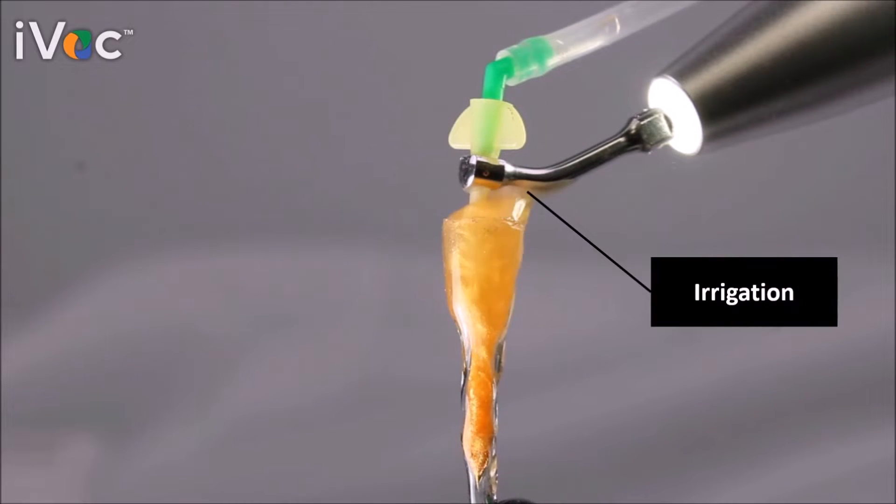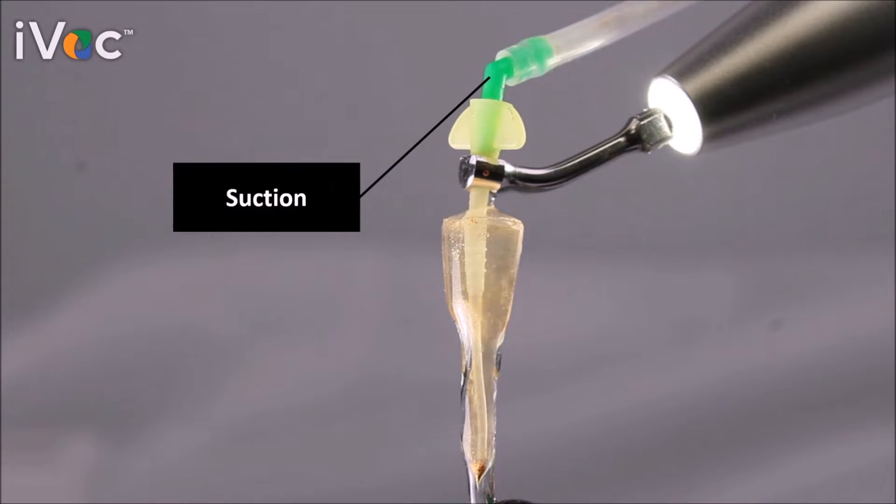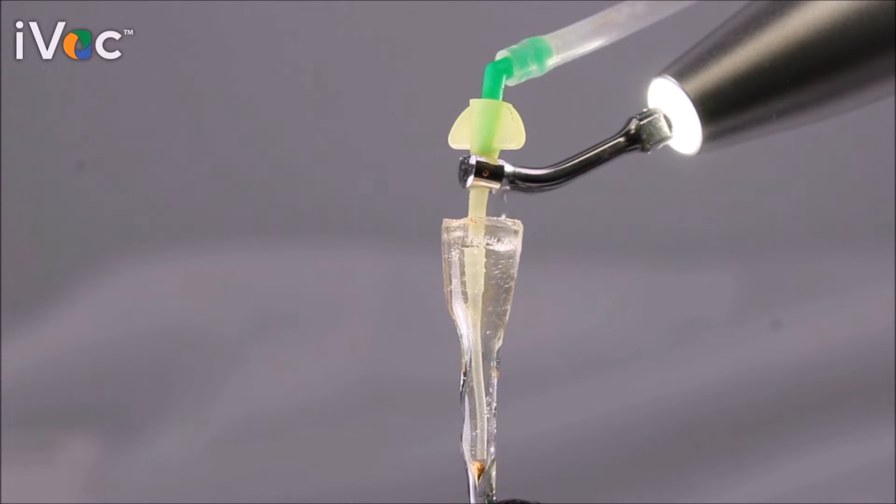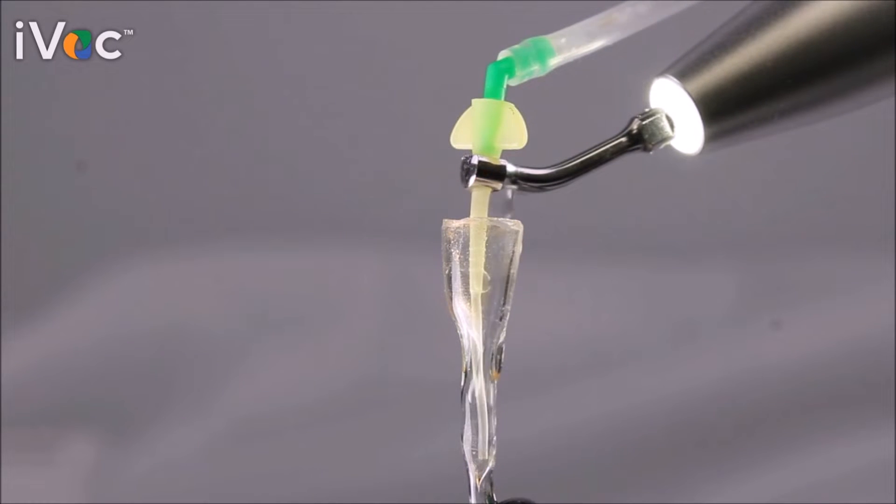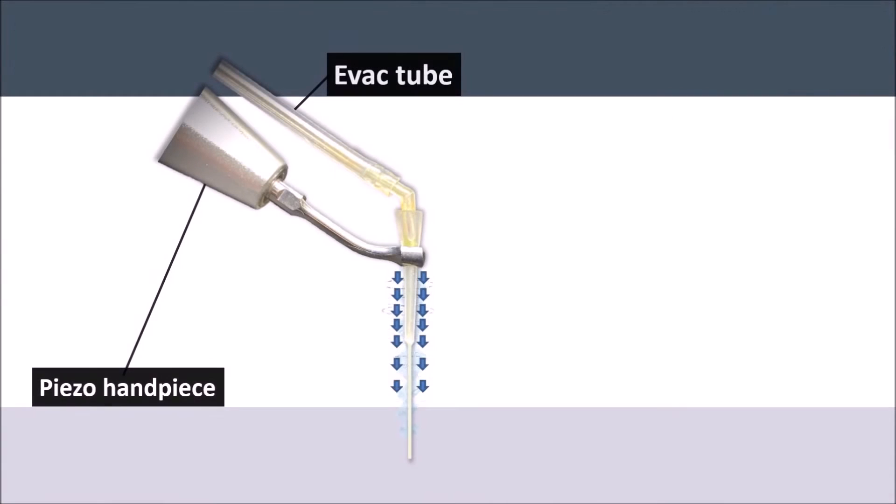From the reservoir, the low vac suction connects to the iVac, providing suction at the tip of the cannula. The vibration helps carry the irrigation fluid throughout the canal extension alongside the external cannula surface and is recollected via the apical opening.